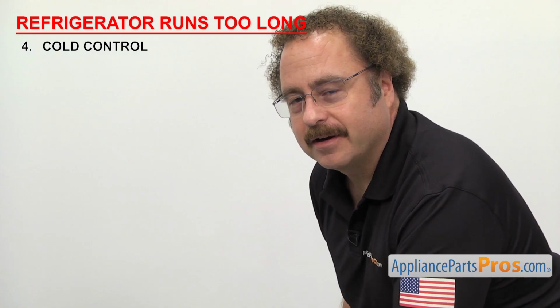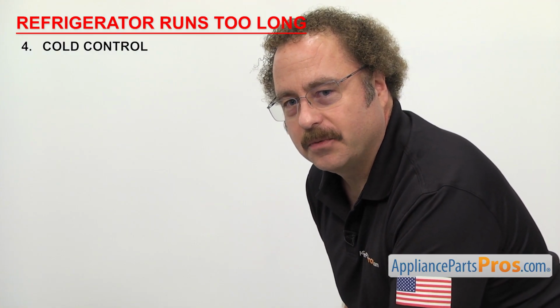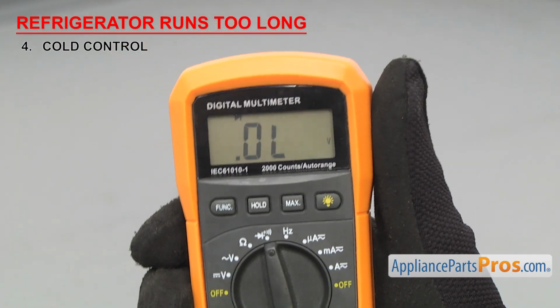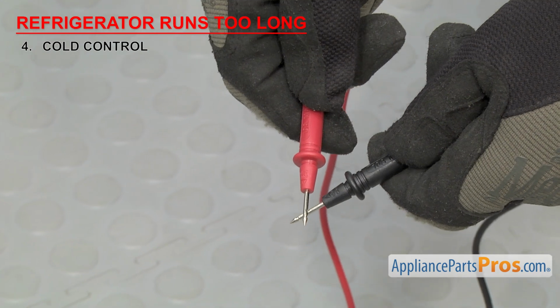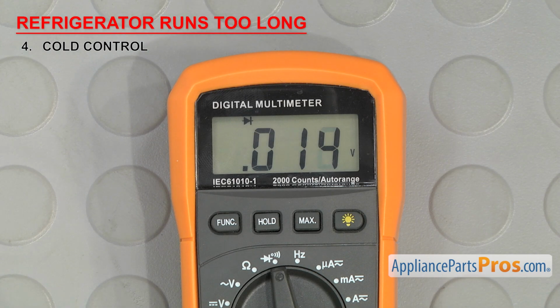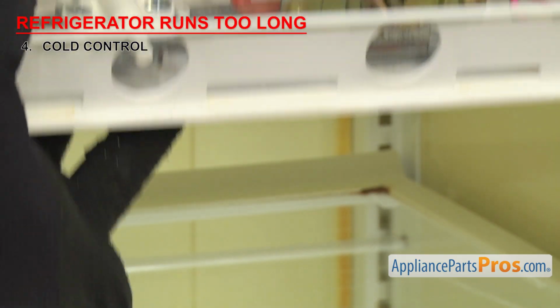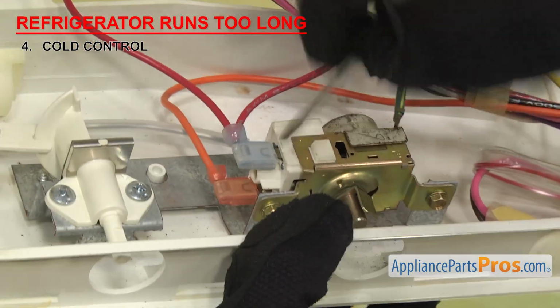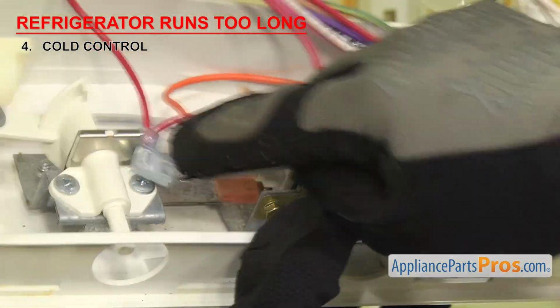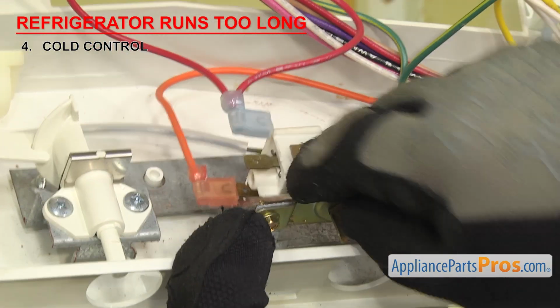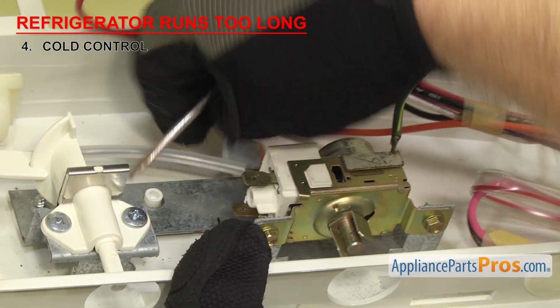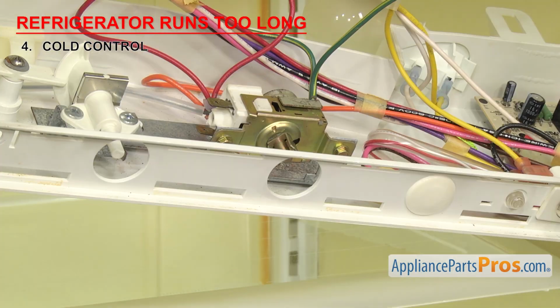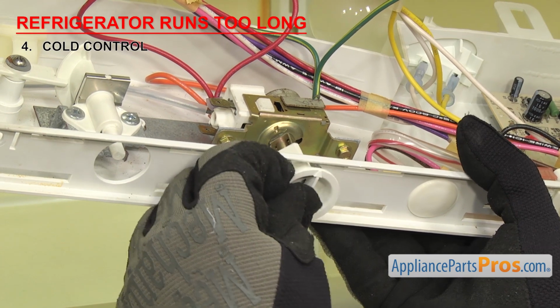In order to see if the part can carry an electric current, we have to test it with a multimeter set to continuity. Once you have it set, touch the probes together to make sure it's working. In order to test the cold control, you'll have to open the control section and remove the wires. Depending upon the design, you may have to remove the knob and screws to get to the wires. You want to make sure the cold control is in the off position.